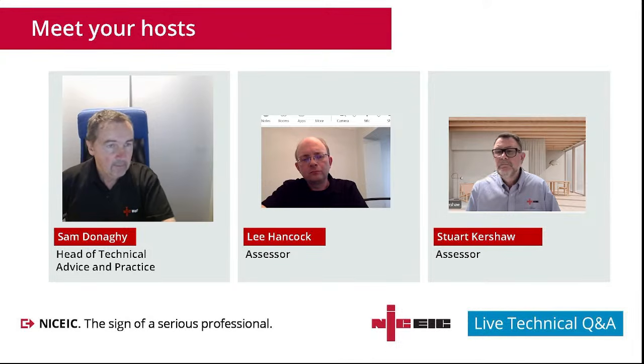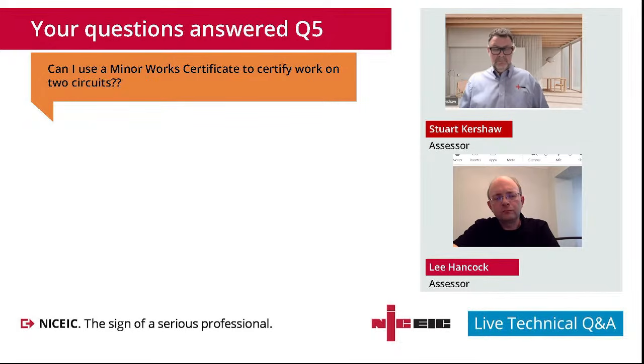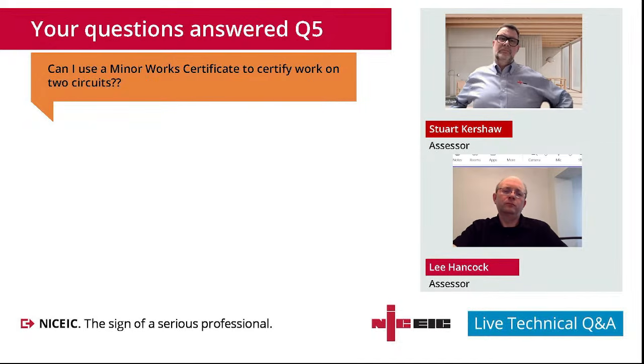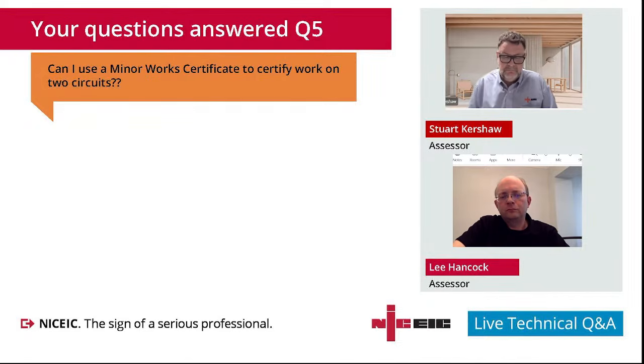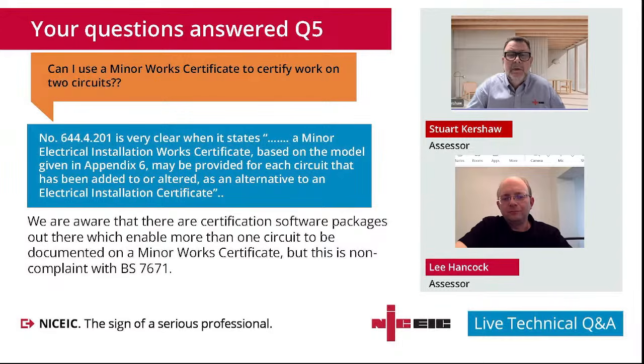We'll take another one because it was one that comes up quite often. So we were asked, can they use a minor work certificate to certify work on more than one circuit? What's our thoughts there, Stu? No, the intention's quite clear. We've had this conversation. I've had this conversation with a number of contractors on assessments who have used, without mentioning names again, a third-party software where they do a multiple minor work certificate. But 644.4.201 states that a minor works certificate shall be issued based on the model in Appendix 6, provided for each circuit that has been added or altered.